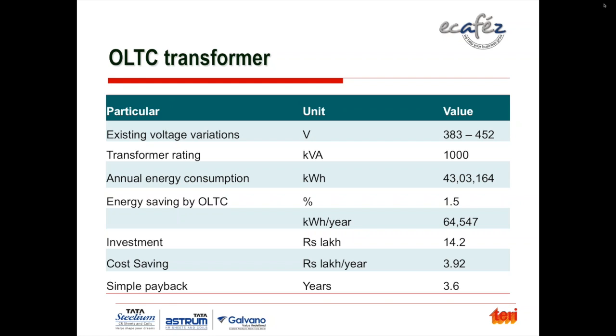And this is the transformer rating: 1000 kVA. Then the annual energy consumption in the unit. The percentage energy saving because of installation of this transformer is only 1.5%, but in terms of units, 64,000 units of energy saved at an investment of 14 lakhs. The cost saving was about 4 lakhs, with a payback period of less than 4 years, 3.6 years.